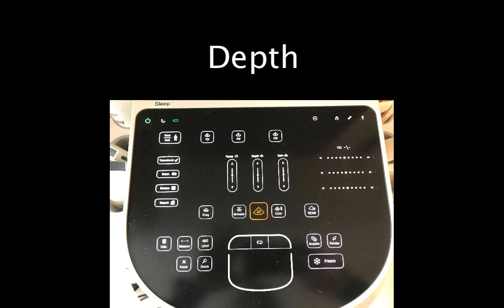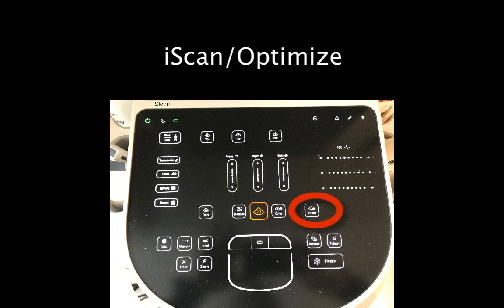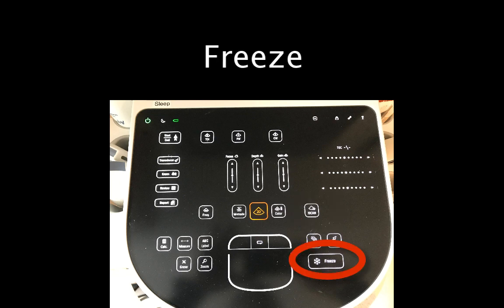The depth can be controlled by sliding your finger along the depth control panel or touching one end or the other of the depth control. Similarly, the same thing can be done with gain. The iScan button or optimize button controls the overall gain. The freeze button is located here.